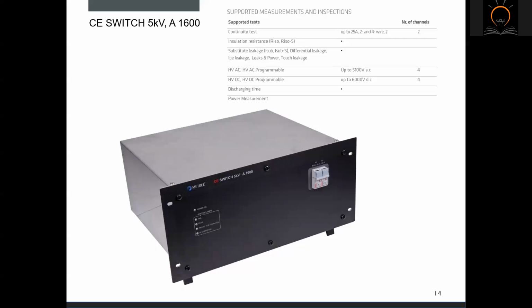Inputs, output connections, and LED connections for controlling the auto sequence flow are integrated. Testing of electrical equipment with multiple connection points is also supported. Different end adapters, or so-called connection boxes, can be connected to the switch. The switch automatically recognizes the connected adapter and prevents applying too high voltages and currents to it. Protection is assured both by hardware and software.